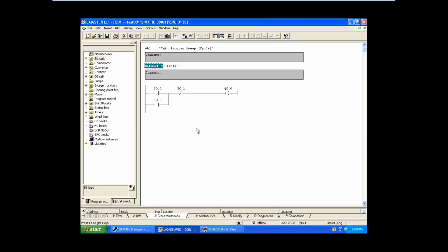Your project may have 100 rungs. In all the rungs, you should include the start push button. Same thing, stop push button or emergency stop. That should be included in all the rungs to stop the process immediately. Right, some in emergency cases, if you press the stop push button, everything should stop. Correct. So start and stop push button, we need to place it in all the rungs. Correct. So in that case, latching is also very important, that I will be explaining in the upcoming chapters.